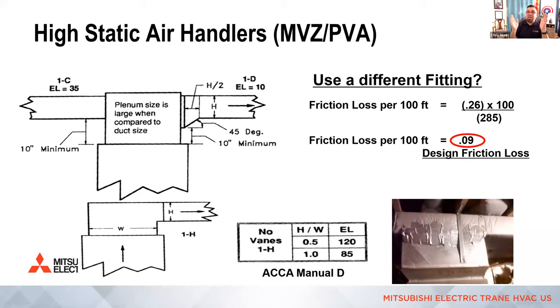You can't pressurize that box. The air, if you can imagine, is hitting the bottom inside that trunk. And it's a bullhead T now. If you were to make the box the full height and stab the trunk into the side, that would be a 35-foot fitting instead of a 120-foot fitting.